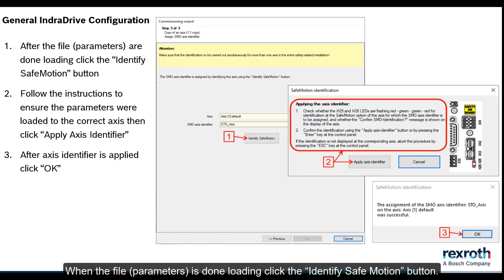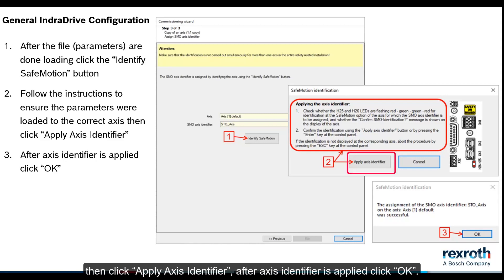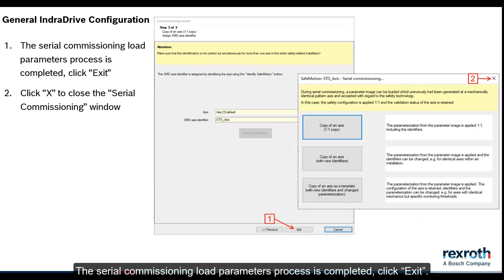When the file is done loading, click the identify safe motion button. Follow the instructions to ensure the parameters were loaded to the correct axis, then click apply axis identifier. After axis identifier is applied, click OK. The serial commissioning load parameters process is completed, click exit.